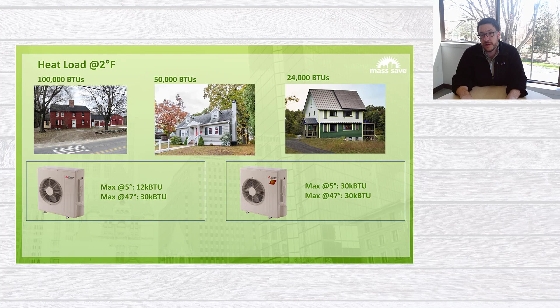You may be asking yourself now, well, how do you know if a home needs 100,000 BTUs or 50,000 BTUs or 24,000 BTUs per hour? The answer is there is a software or a calculation called a Manual J heat load report. In that report, you would go and measure all of the walls, all of the windows, the level of insulation in the attic, the insulation along the floor, how leaky the home is, and you put all of those inputs into a calculator, and it will tell you exactly how many BTUs per hour the home will need for its heating load as well as for its cooling load.